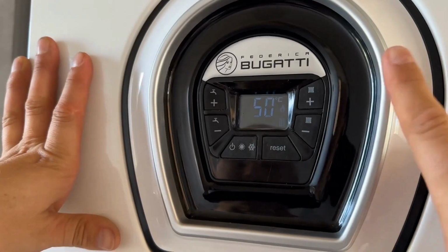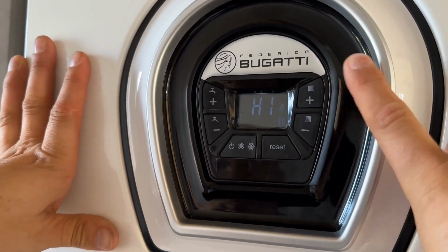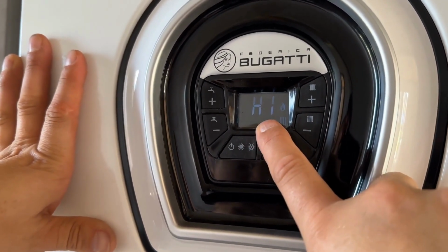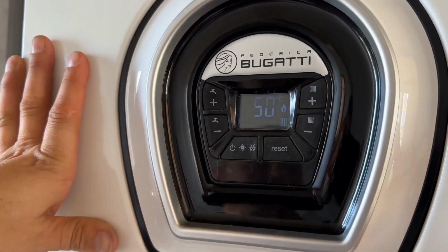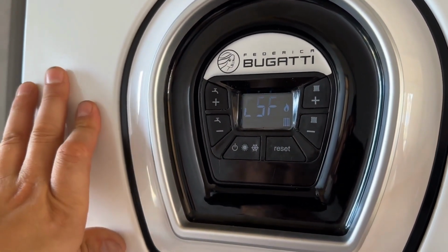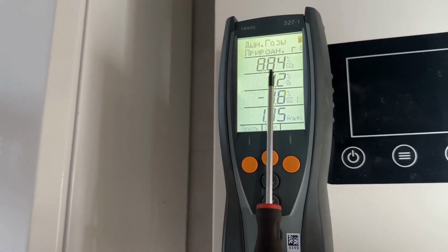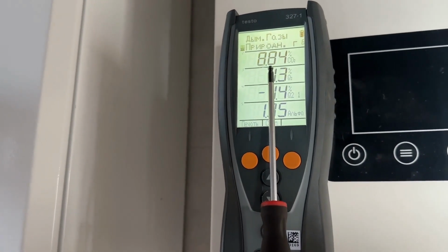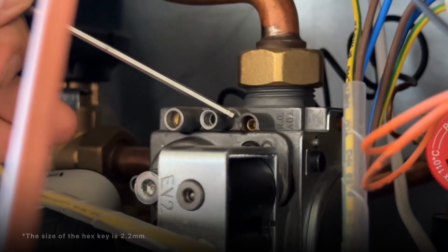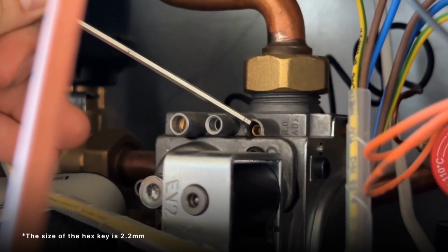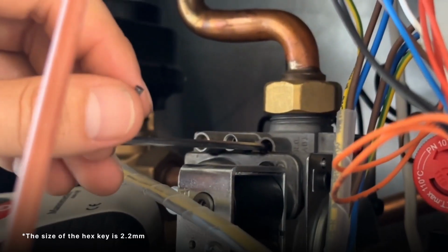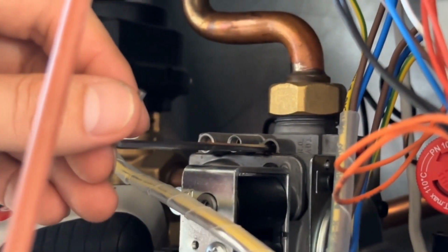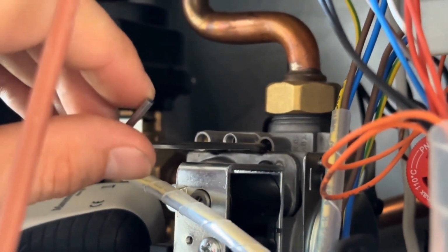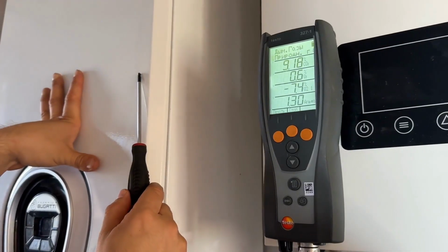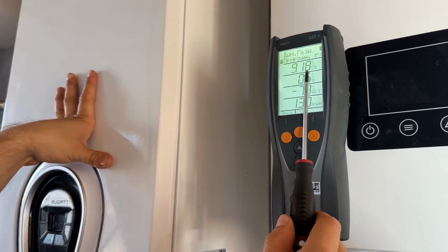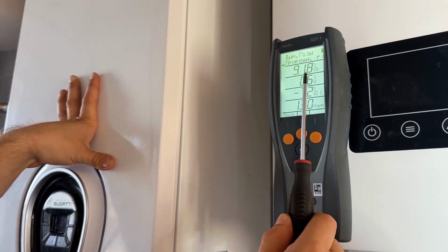To do this, in the chimney sweep mode, we press the plus button. The display shows the message high, and the boiler reaches maximum power. At maximum power, the level of carbon dioxide, CO2, should be 9.2%. The adjustment of the maximum power is carried out using a 2 mm hex key. Rotate counterclockwise to increase the concentration of CO2, and clockwise to decrease it. Don't forget to close the lid, after which we wait for 1 minute to achieve the desired results.